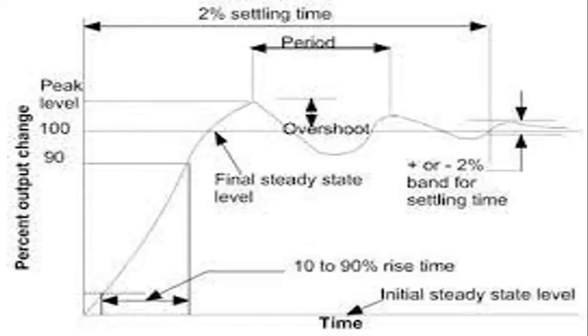For this step input, the instrument output responds by going beyond 100% output change — it overshoots, then comes down, then goes up again. The difference between two consecutive peaks is called the period. The overshoot and undershoot beyond the maximum point gradually reduce and the output settles down over time.